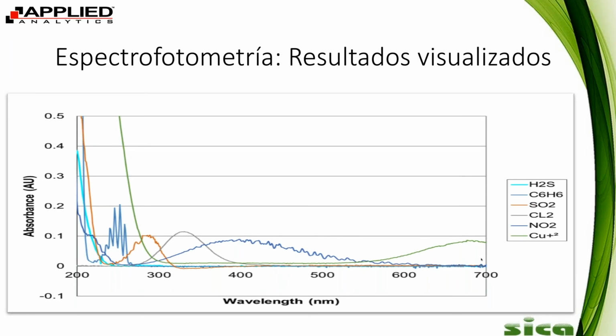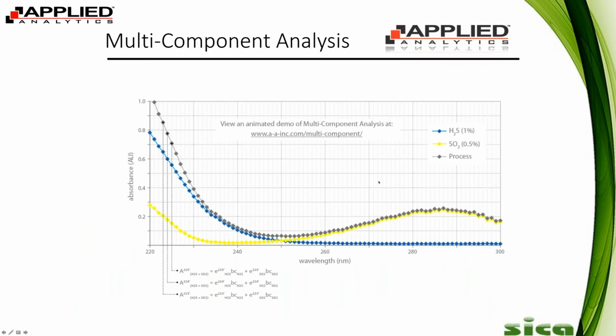So, multi-component analysis. As you can see here, you can see the H2S curve in blue, the SO2 curve in yellow, and then an overall absorbance curve that's gray. What our spectrometer does is calculate an absorbance value at each wavelength integer. And what we're able to do is deconvolute the total absorbance, say, speciate it into H2S and SO2, basically by running a system of equations where you have two unknowns and two equations. You're able to find the absorbance value at each wavelength integer throughout the calibration. So that also allows you to cross-reference your measurements.